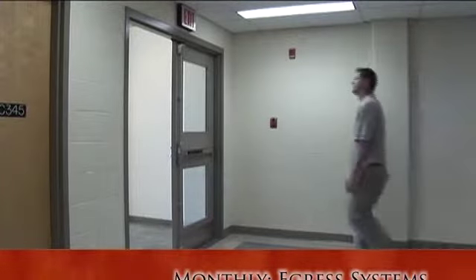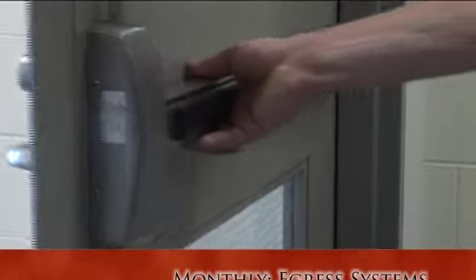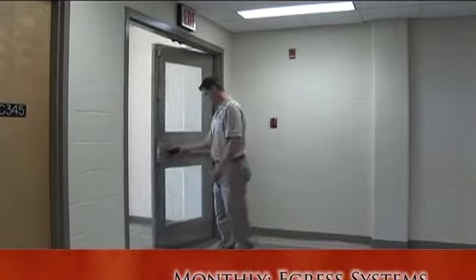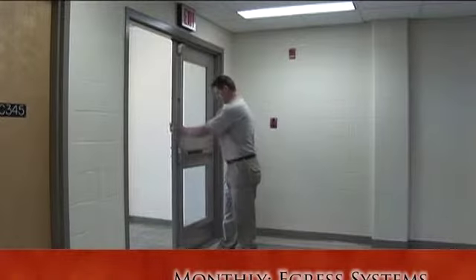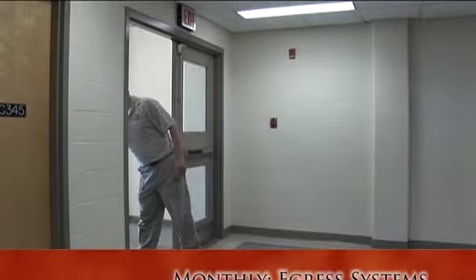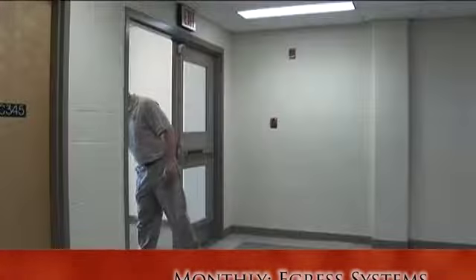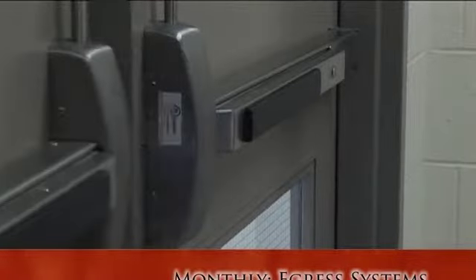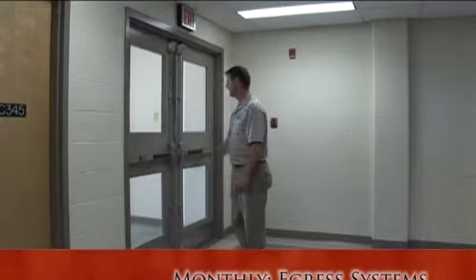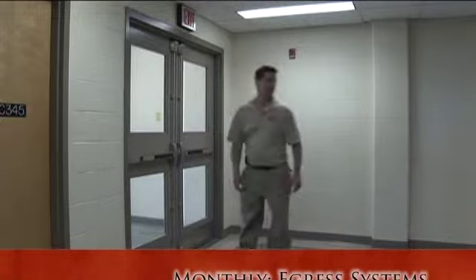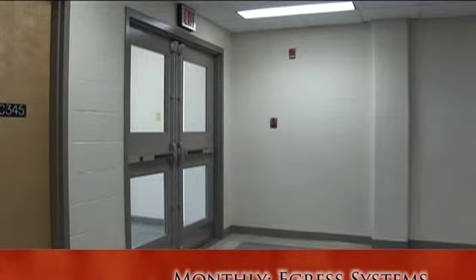Test all fire separation door hardware, including latches, hinges, and door closers, etc., to make sure that they operate properly while manually opening and closing the door. Now, when they're opened, make sure that they return to their closed position and that they latch. If door closers, latches, or hinges don't operate properly, take corrective action or advise your supervisor that this work is necessary.